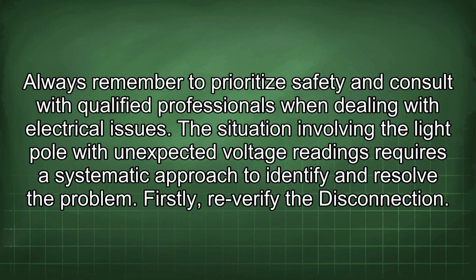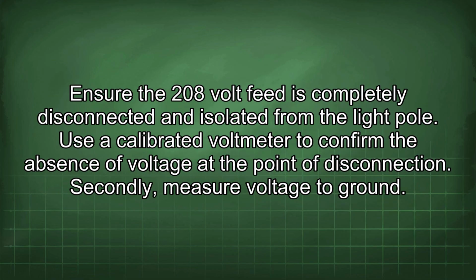The situation involving the light pole with unexpected voltage readings requires a systematic approach to identify and resolve the problem. Firstly, re-verify the disconnection. Ensure the 208-volt feed is completely disconnected and isolated from the light pole. Use a calibrated voltmeter to confirm the absence of voltage at the point of disconnection.